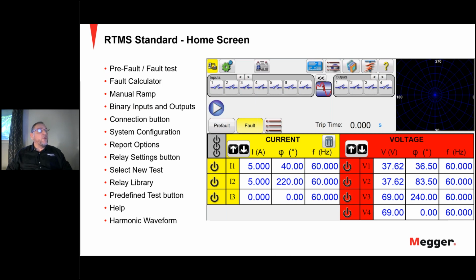So first of all, looking at the home screen, the first is your pre-fault fault test. Pre-fault fault is very helpful when doing simple timing tests and fault finding on relays. This is an especially helpful tool for the user who has to adjust mechanical contacts on electromechanical relays. The next one is the fault calculator.